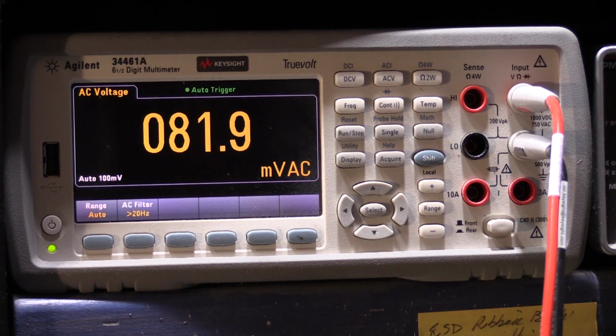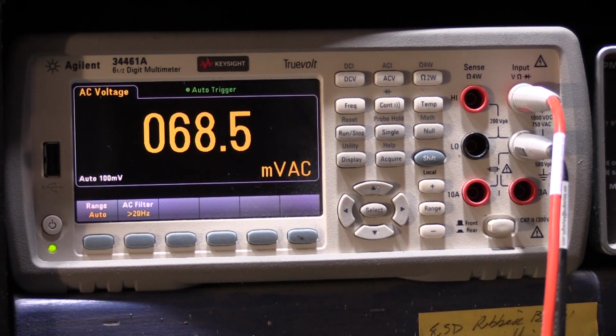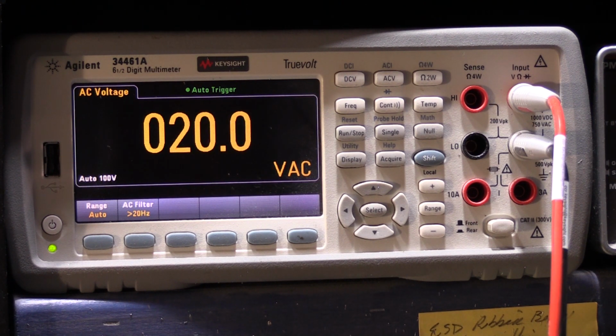I've changed my setup back. We're now on the top input, which is for volts, on AC voltage. I'm going to connect the probes of the meter to the output of the transformer. Now we're at 20.1 volts, because as the input voltage into the shop varies, the voltage coming out of the transformer will vary. So obviously our line voltage has increased a little - maybe all the neighbors have turned off their air conditioning.